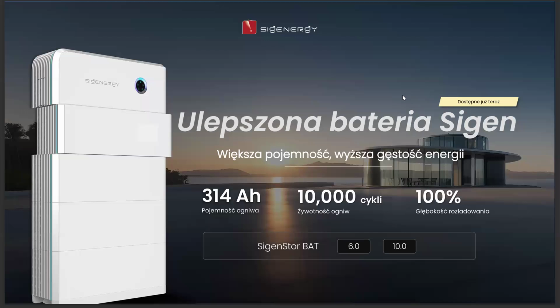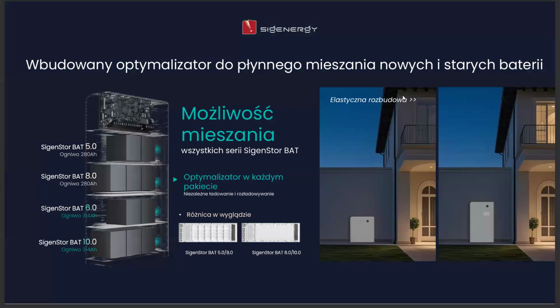Slide 24. Battery architecture, independence and expansion freedom. 1. DC-DC converter in every module. The key to understanding the strength of our battery storage system is its internal architecture. In Sigen, each battery module has its own individual DC-DC converter. What does this mean in practice? Each module in the stack operates as a fully independent unit.